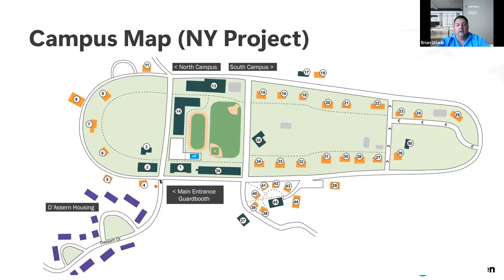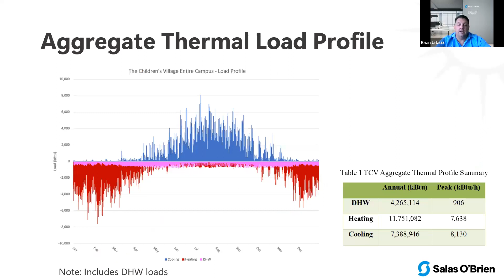So we wanted to take advantage of that diversity, and there was significant savings in bore field cost by interconnecting all these buildings. Again, you go through the thermal load process, develop an aggregate, figure out your groupings, figure out where to put your thermal resources, what's available, and the strategic locations to balance out the ambient temperature loop so everybody's getting the same temperatures for efficiency.